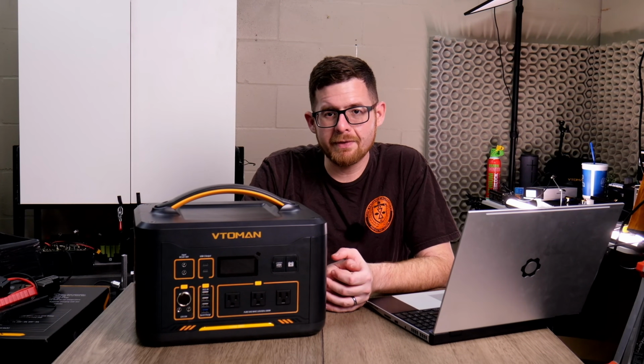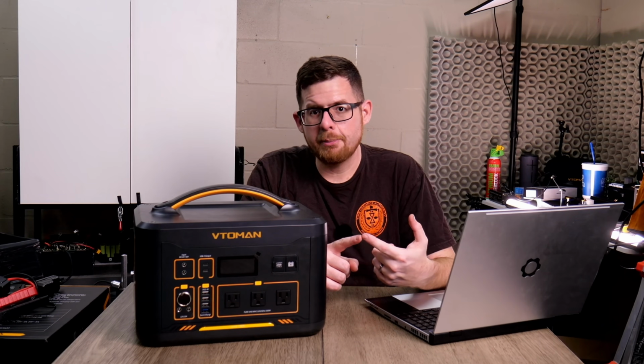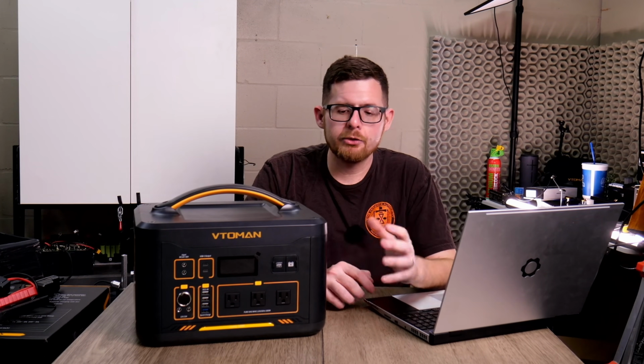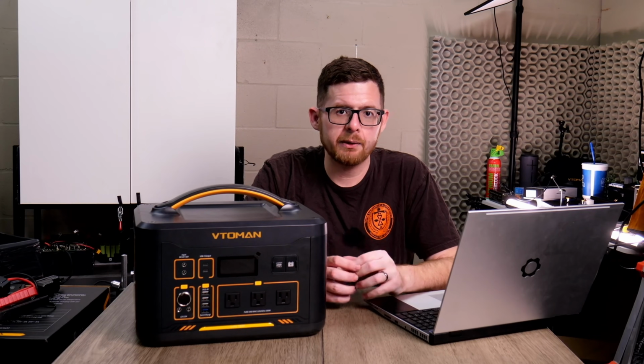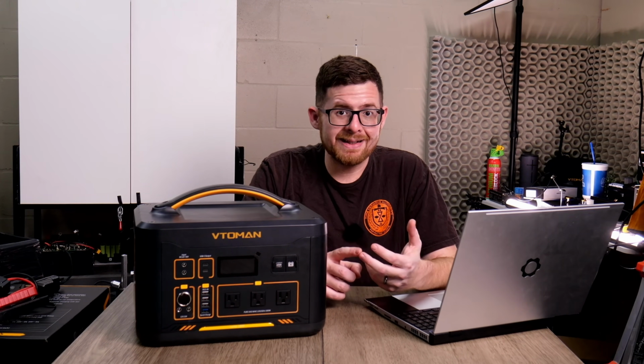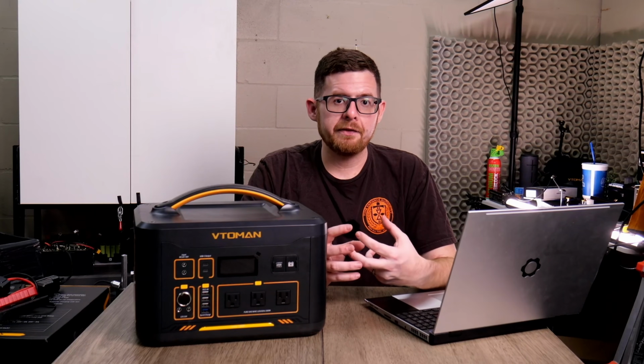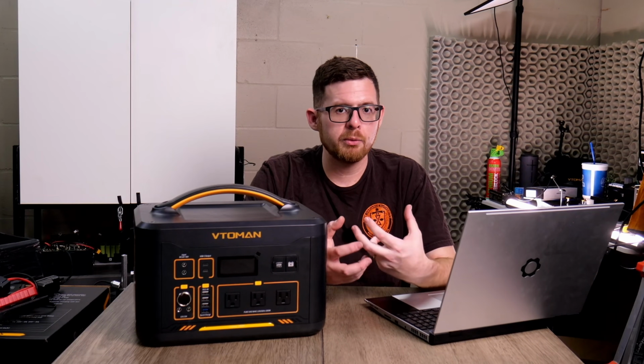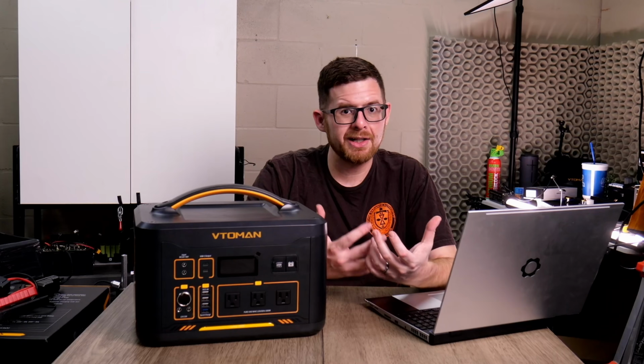And when I'm working on something for a hurricane, I don't necessarily want an additional 200 degrees on top of the 100 degrees and 100% humidity already outside. Ultimately, this unit is a pass for me. It doesn't have the capability of running some of the high-end loads you'd need it to run because of that grounding fault. The componentry inside really feels piecemealed together, like they're taking parts out of the waste bin, throwing them together, and then trying to charge a premium for them.